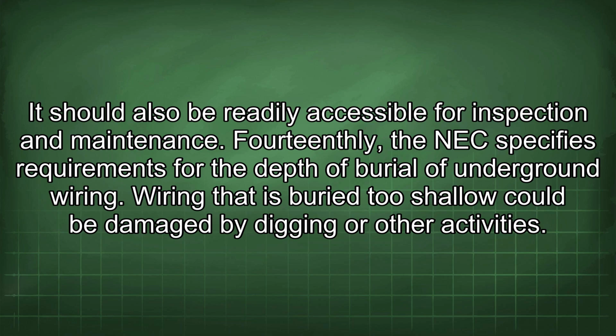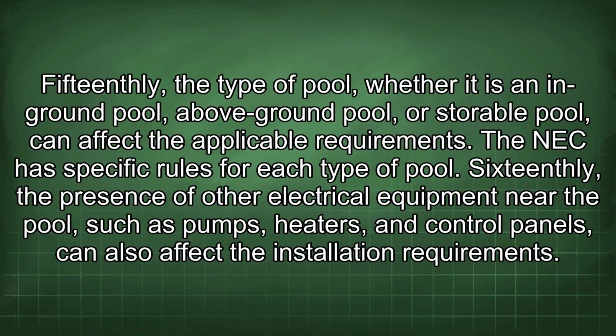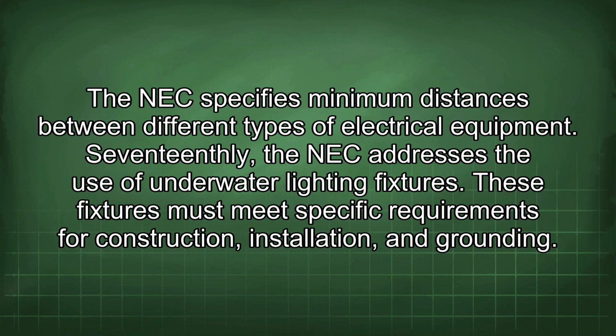14thly, the NEC specifies requirements for the depth of burial of underground wiring. Wiring that is buried too shallow could be damaged by digging or other activities. 15thly, the type of pool, whether it is an in-ground pool, above-ground pool, or storable pool, can affect the applicable requirements. The NEC has specific rules for each type of pool. 16thly, the presence of other electrical equipment near the pool, such as pumps, heaters, and control panels, can also affect the installation requirements. The NEC specifies minimum distances between different types of electrical equipment. 17thly, the NEC addresses the use of underwater lighting fixtures. These fixtures must meet specific requirements for construction, installation, and grounding.